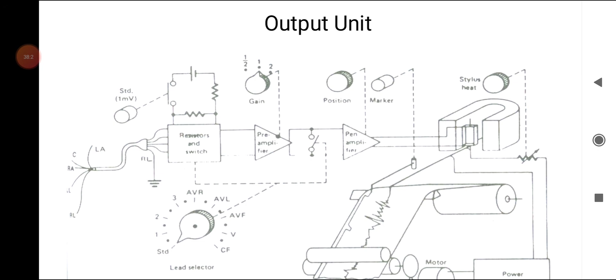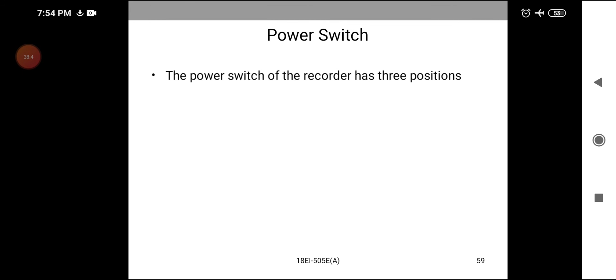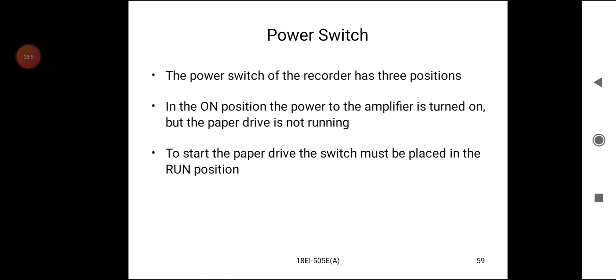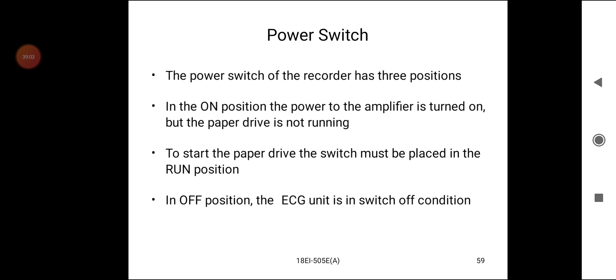The output unit is a cathode ray oscilloscope or a paper chart recorder. The power switch of the recorder has 3 positions. In the on position, the power to the amplifier is turned on, but the paper drive is not running. To start the paper drive, the switch must be placed in the run position. In the off position, the ECG unit is switched off.